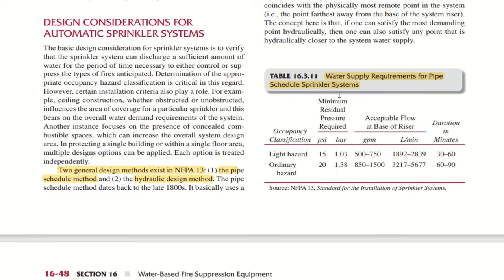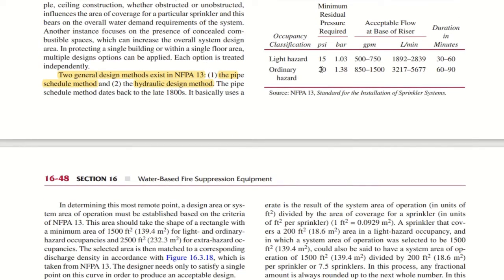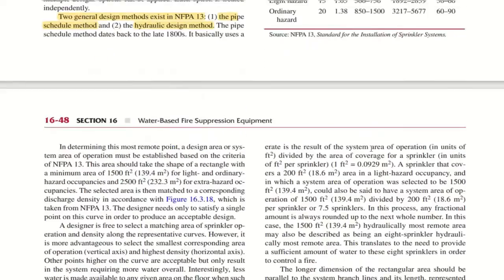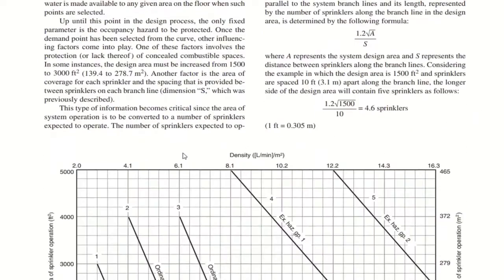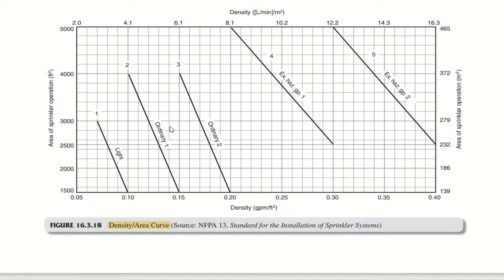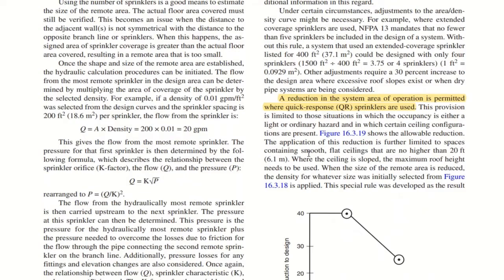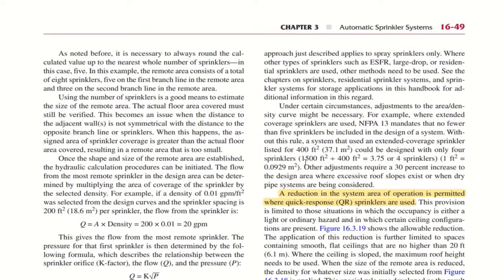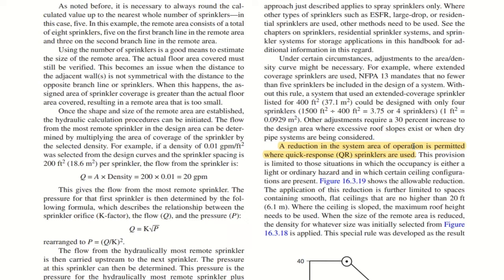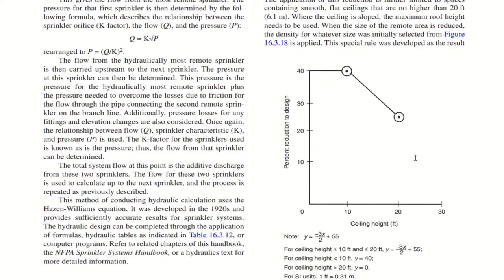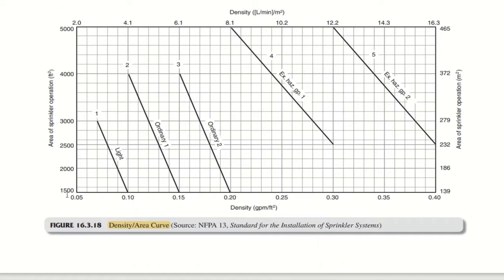So this is for pipe schedule sprinkler system, which is a very important subject to be remembered, and also this might be asked in an interview as well. So here once again you can see the density area curve. This we already discussed in our earlier chapter. If you are using quick response sprinklers, there are special design considerations to be taken. A reduction in the system sprinkler or system area of operation is permitted where quick response sprinklers are used. So when we are considering the hydraulically designed area, for example you have light hazard occupancy, and the hydraulically most demanding area is 1500 square feet at 0.1 gpm per square feet.